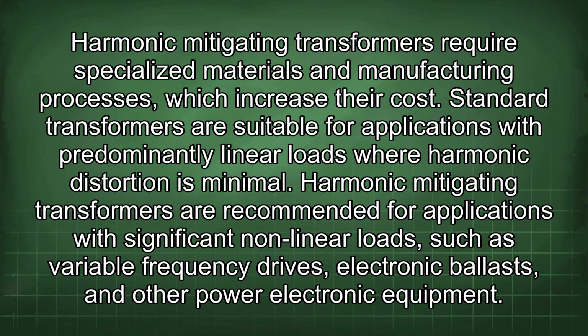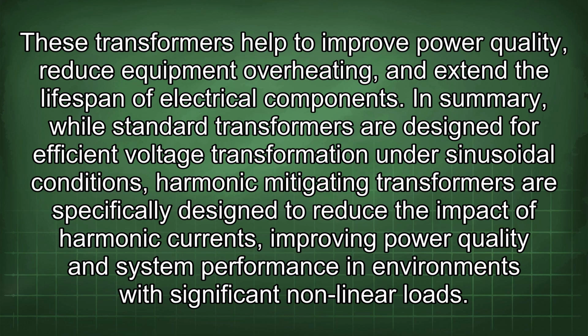Harmonic mitigating transformers are recommended for applications with significant nonlinear loads such as variable frequency drives, electronic ballasts, and other power electronic equipment. These transformers help to improve power quality, reduce equipment overheating, and extend the lifespan of electrical components. In summary, while standard transformers are designed for efficient voltage transformation under sinusoidal conditions, harmonic mitigating transformers are specifically designed to reduce the impact of harmonic currents, improving power quality and system performance in environments with significant nonlinear loads.